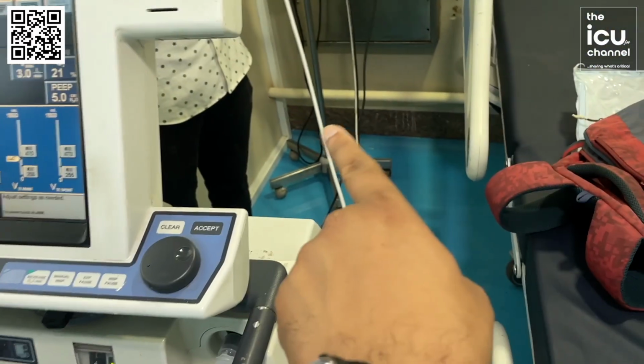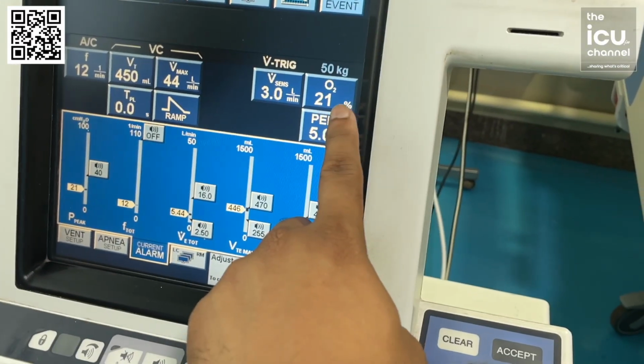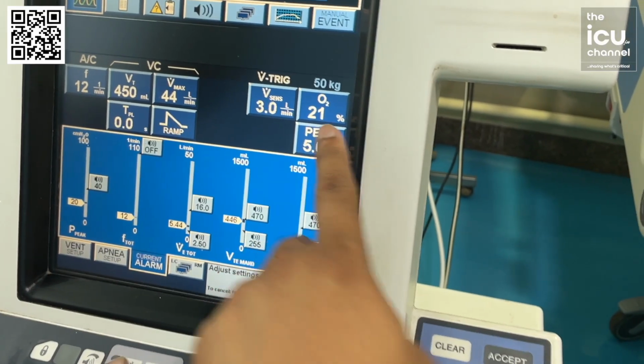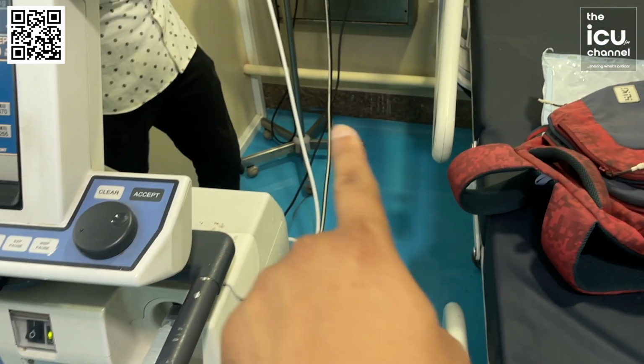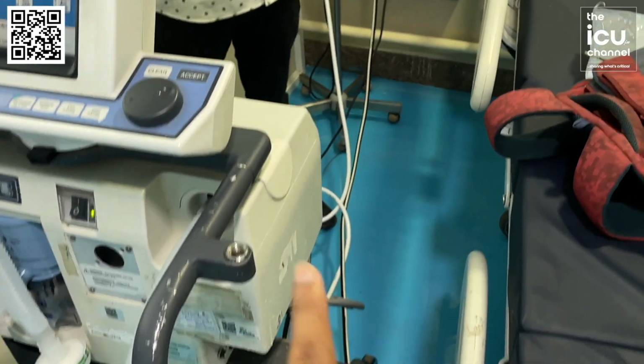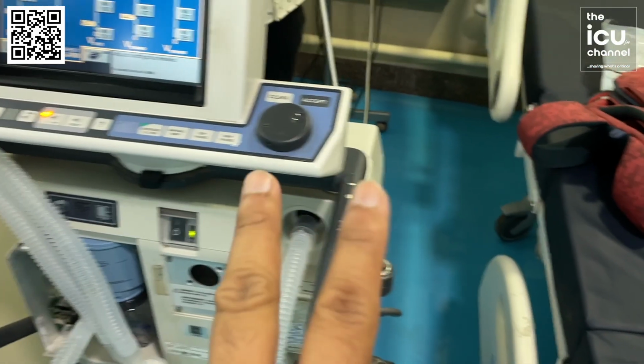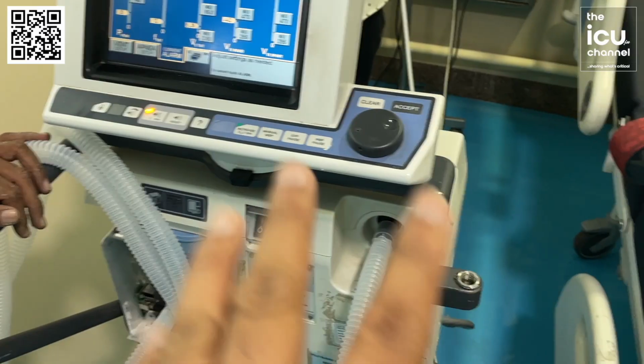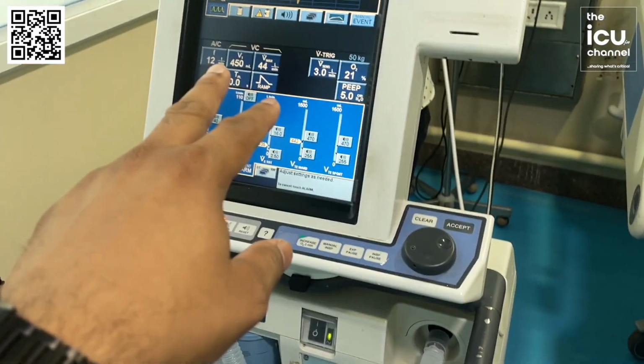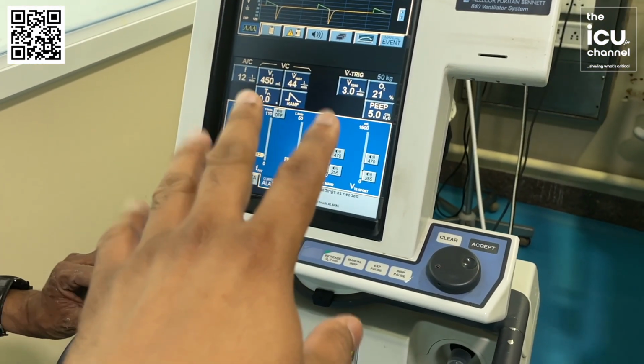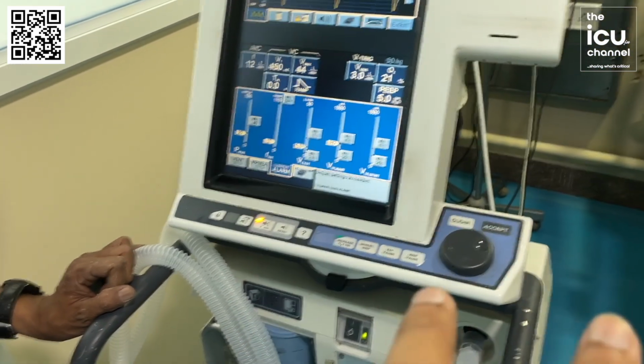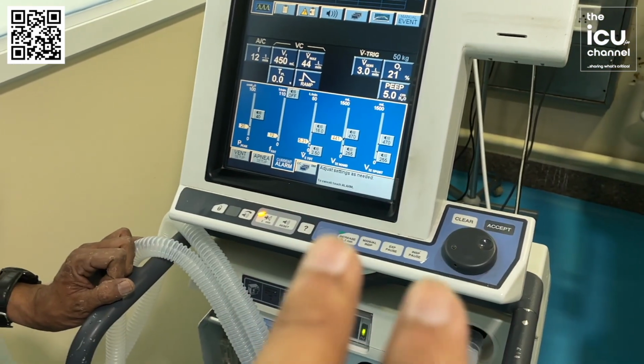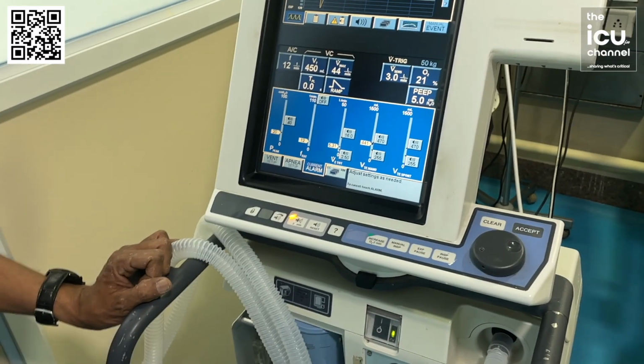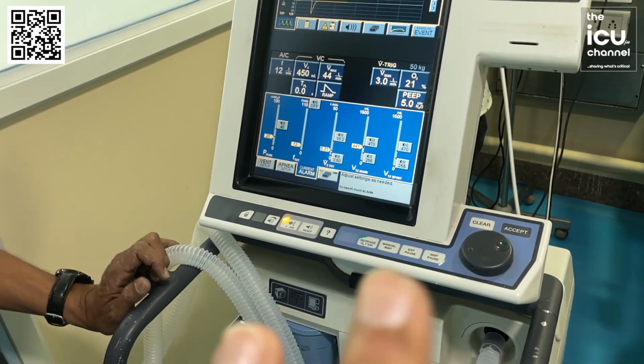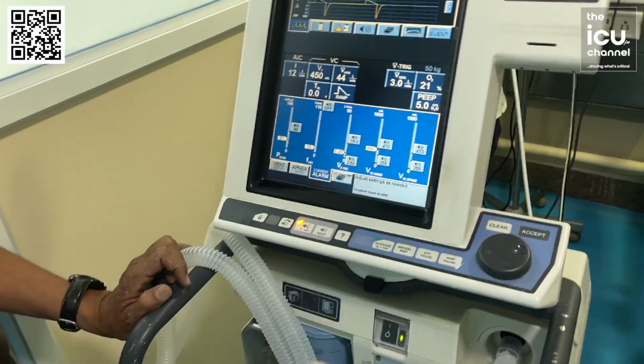That means this much tidal volume we want the patient to get delivered. So what is happening now? And this is the amount of FiO2 which you want. The oxygen and the air are coming to the inspiratory side of the ventilator. Then they will pass both the flow sensors, and they will sense whether this much tidal volume is getting delivered or not. After that, they will go to the pressure sensors, so that there is a safety valve sort of thing, checking whether the pressure is fair enough or not, exceeding or low. And then they will go to the mixer.